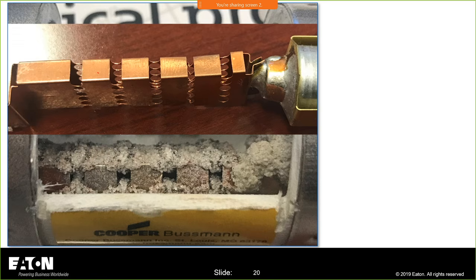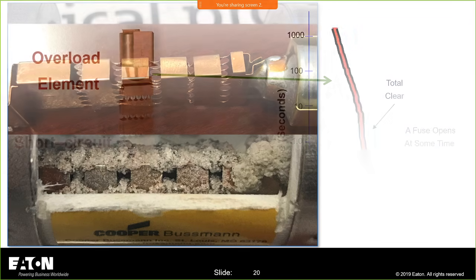So these little pinch points right in here, that's what does the high current short circuit. It turns that sand into fulgurite, creates and isolates the system. And an interesting fact, if you've opened a few fuses and you're not sure why and how much current you're really drawing because you don't have it metered, then you could x-ray these and see how many of these pinch points have cleared that fault, or maybe just this one opened. And by knowing those little details, our scientists at Bussmann can tell you approximately how much current was flowing through that device when it opened.